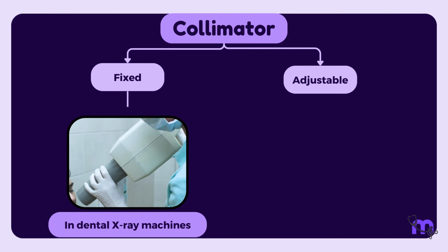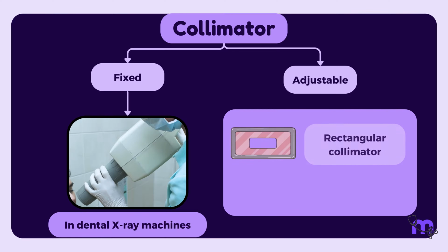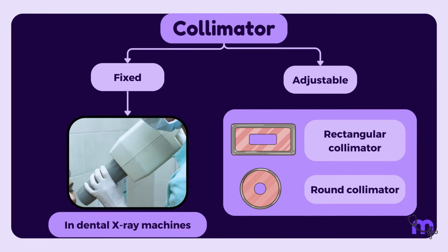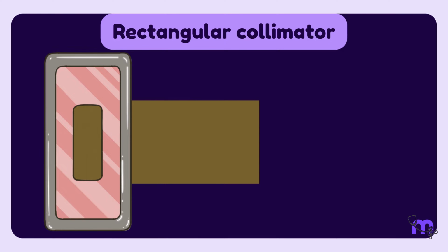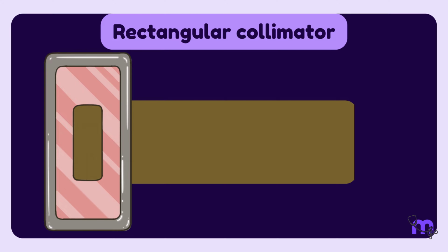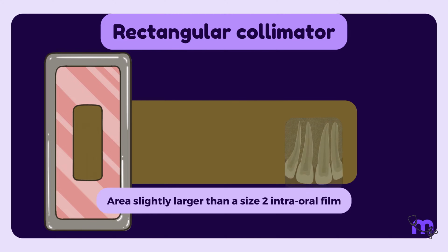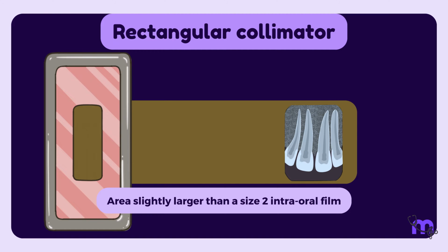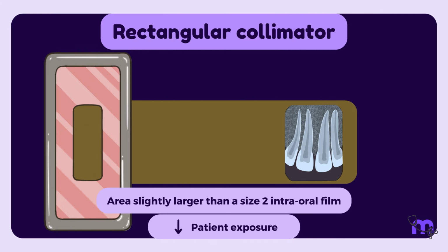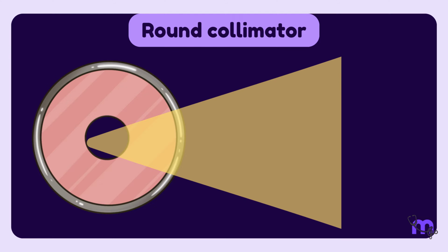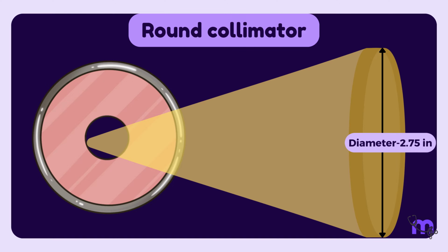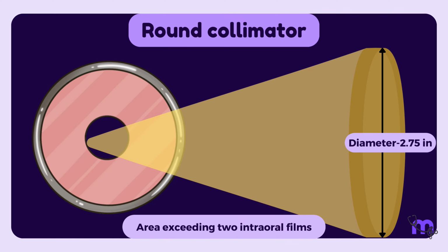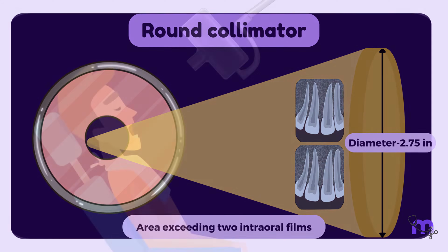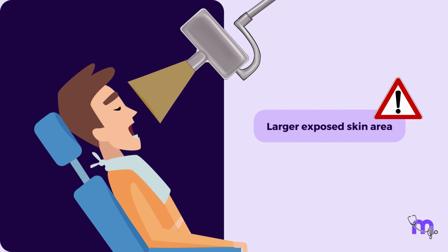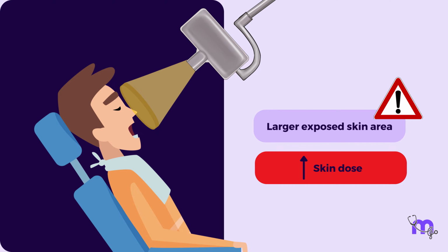In dental X-ray machines, we use fixed collimators, which can be rectangular or circular, depending on the shape of the hole. Rectangular collimators restrict the size of the X-ray beam to an area slightly larger than a normal adult intraoral periapical film or a size 2 intraoral film, significantly reducing patient exposure. Circular collimators produce a cone shaped beam with a diameter of 2.75 inches, exceeding the size of two intraoral periapical films. This results in a larger exposed skin area, resulting in a higher skin dose for the patient.